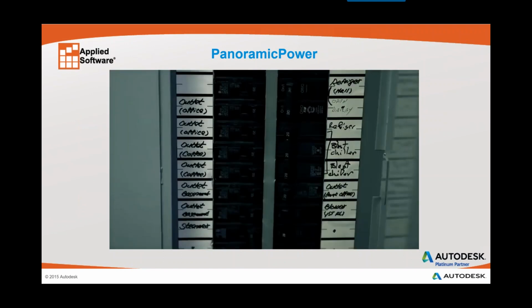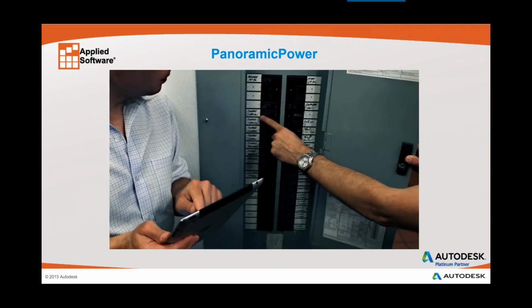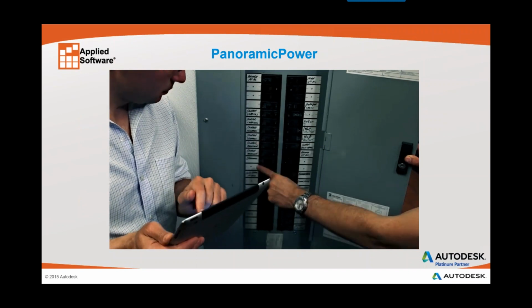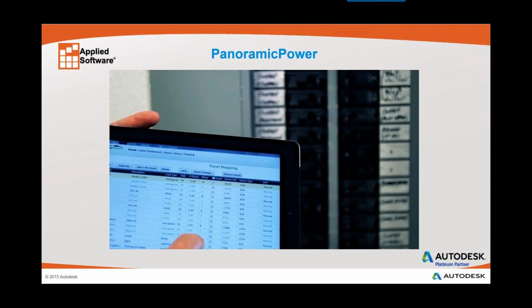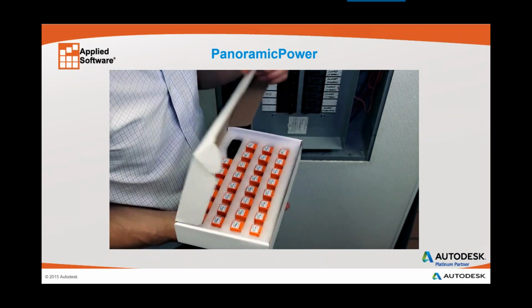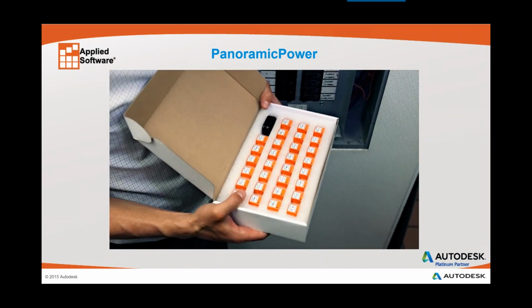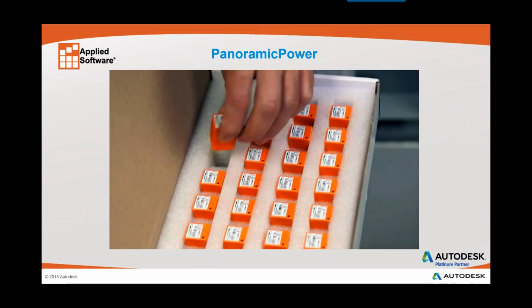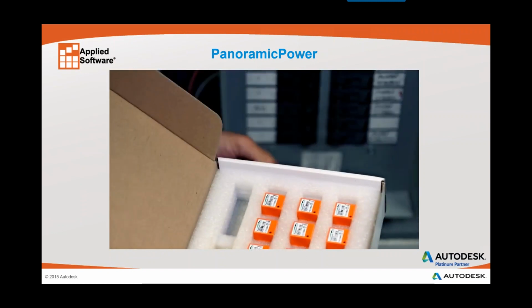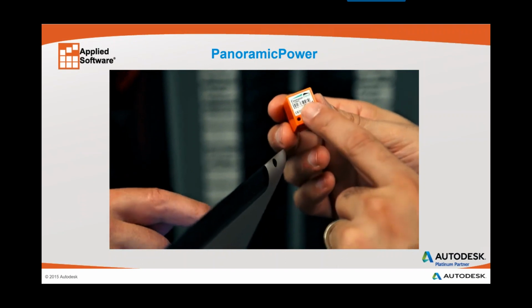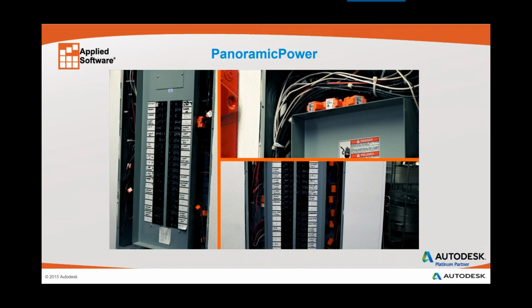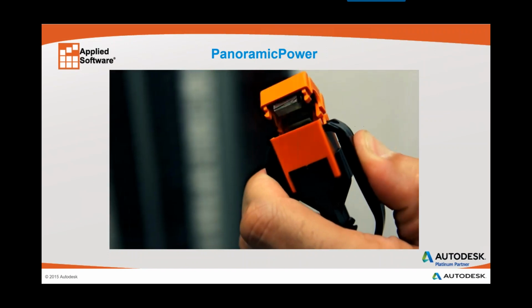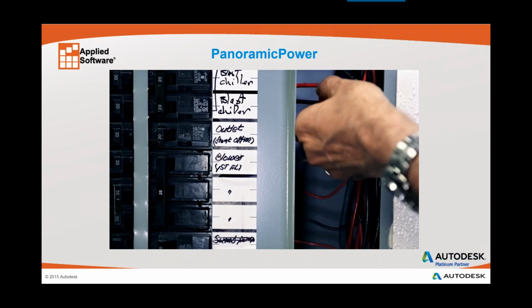Installation starts by identifying the devices and circuits to be monitored and mapping them into the system using our deployment tools, which control and manage the installation process of unlimited endpoints across multiple sites. Our unique, miniature, non-invasive, self-powered and wireless sensors enable organizations to quickly and cost-effectively collect real-time energy consumption data for an unlimited number of individual loads within a facility. Each sensor has a unique ID that is matched to a physical circuit. The sensors are easily installed on all panel boards within the facility with a simple snap and clip, and without disruption or the need to disconnect any wires.